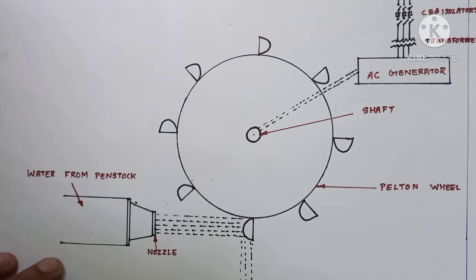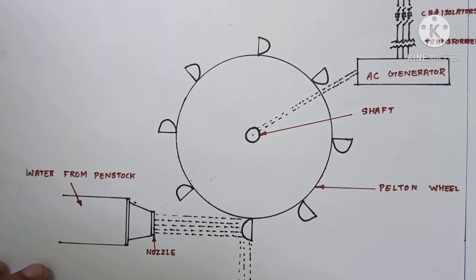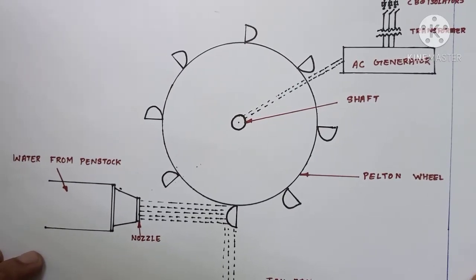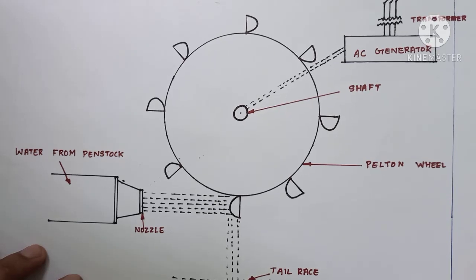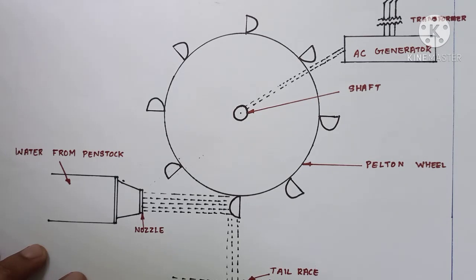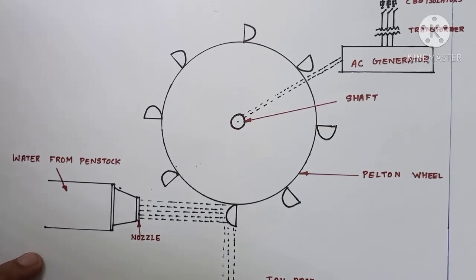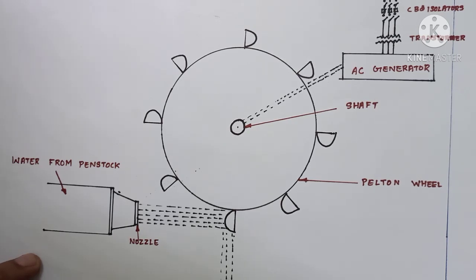Penstocks are made of very strong materials like steel or reinforced concrete. Here we can see a Pelton wheel turbine. Based on the action of water on the moving blade, turbines are classified into two categories: impulse turbines and reaction turbines. Impulse turbines include the Pelton wheel and are mainly used for high heads — almost above 200 meters. In Kerala, the largest hydroelectric power plant is the Moolamattom power plant in Idukki district, with an installed capacity of 780 megawatt and a speed of 375 RPM; due to the availability of high head, Pelton wheel turbines are installed there.